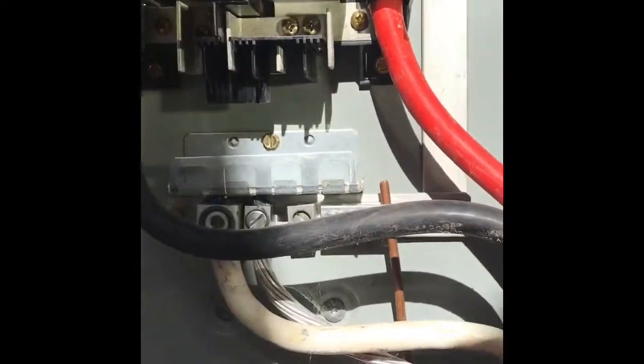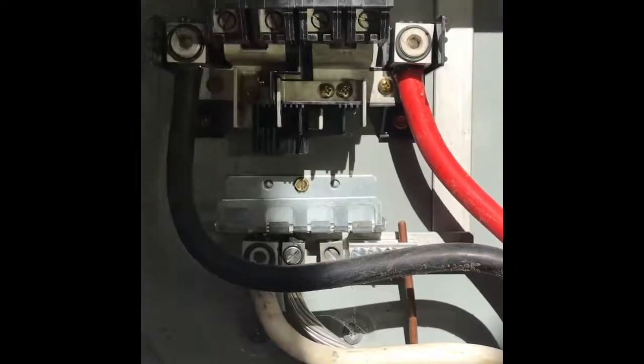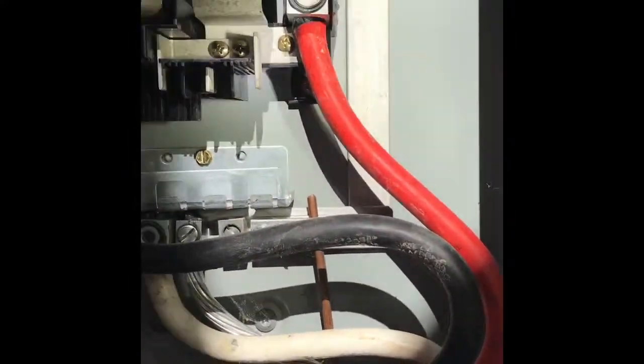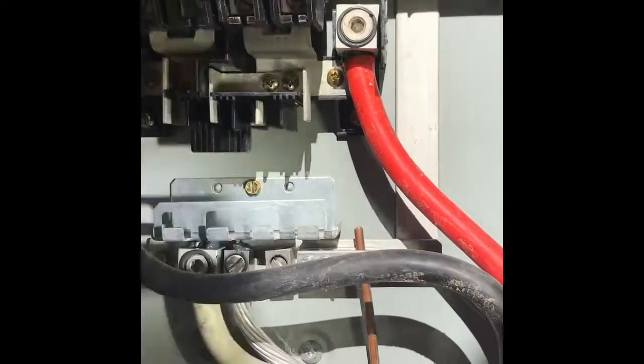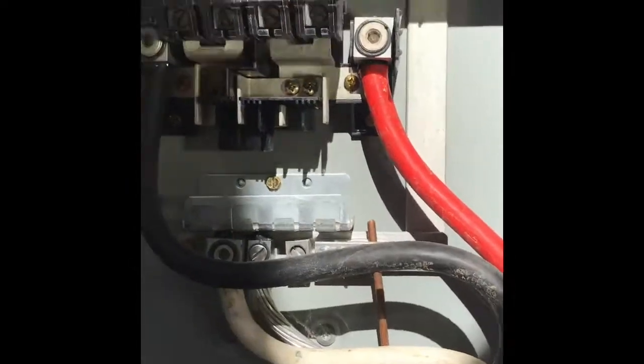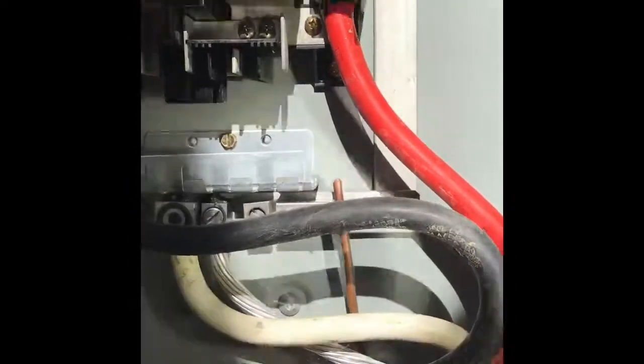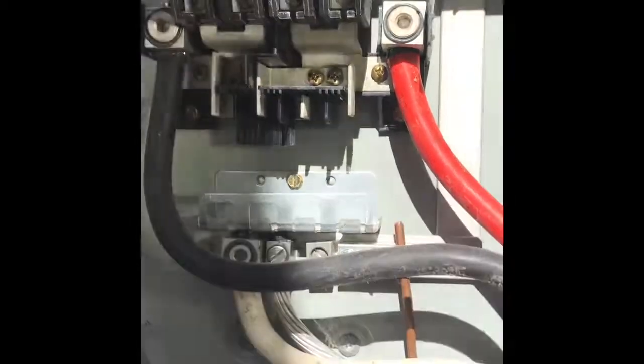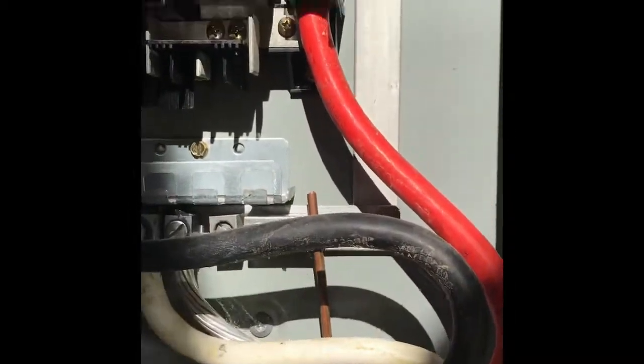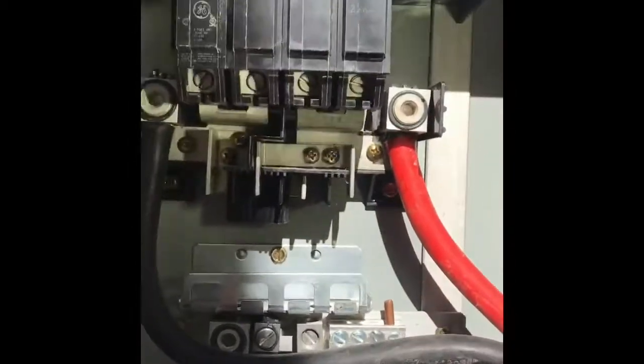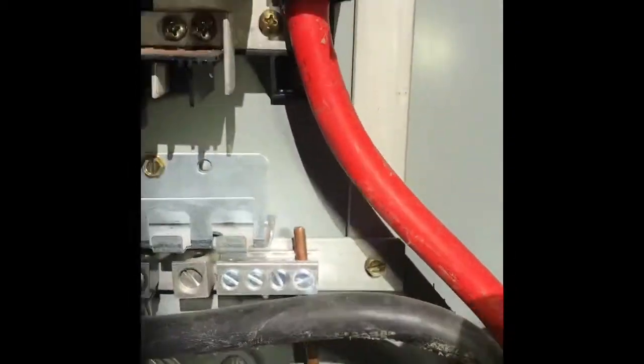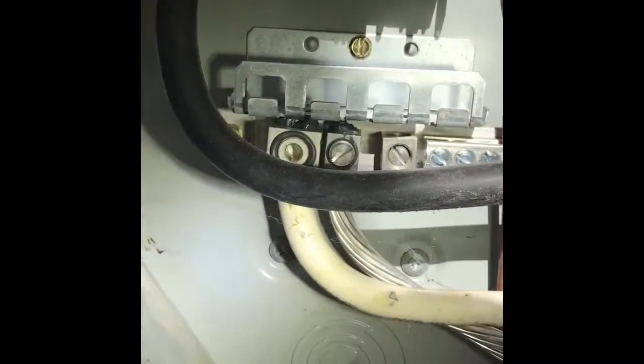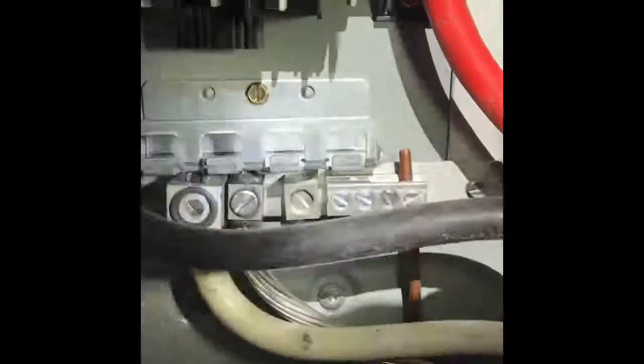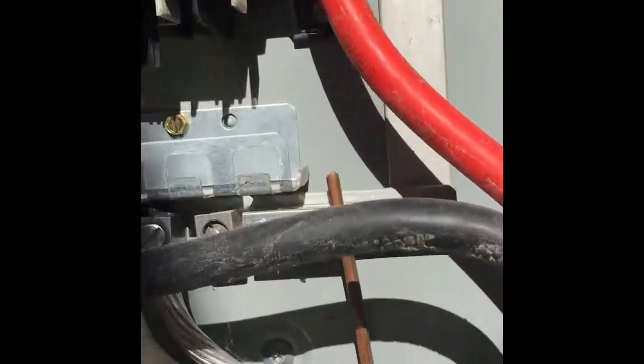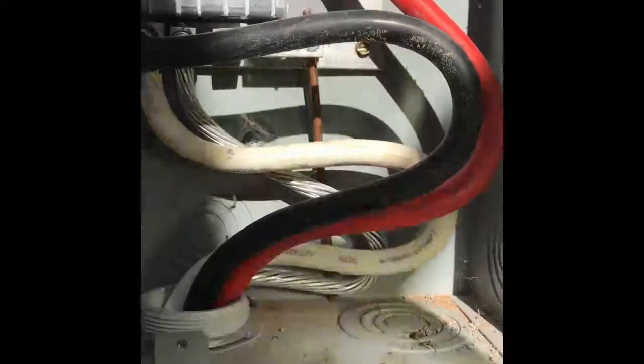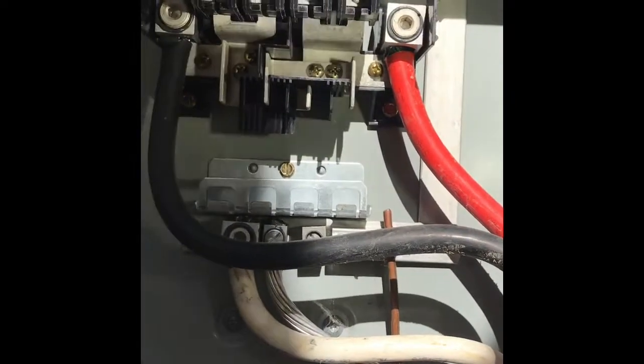So typically, or sometimes 3 feet or less. But typically when that condition happens by code and for safety, what they'll do is put a local disconnect on the exterior. But what happens is actually this disconnect turns into the main panel. So on a home that's set up like this, the exterior single 200 amp breaker is actually the main panel for the whole house. You can tell it's the main because it's on 200 amp. You can see right there the grounding system and the neutral system. For the neutral, it's bonded together on the same bar, which can only happen at the main panel. So even though this panel only has one breaker in it, it constitutes the main.